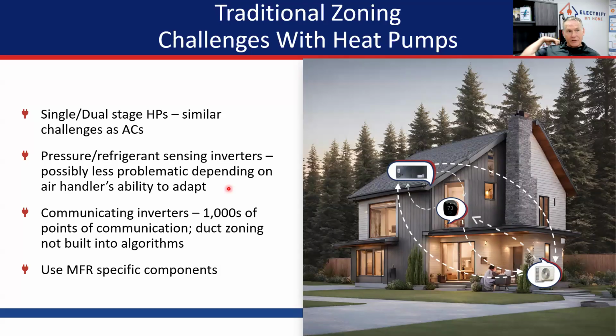That is not a bad solution with zoning, because you're just going to make that refrigerant artificially cooler by slowing down some of the airflow. So that will slow the outdoor unit down, but most of those units come with a single speed ECM blower motor, which the zoning can take out. Now, maybe the unit's going to transition between stages, but we're going to be using blower motors.